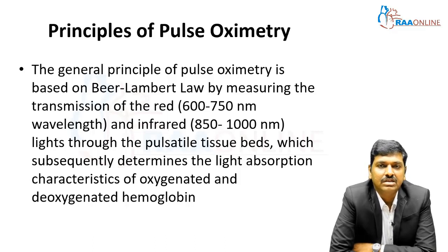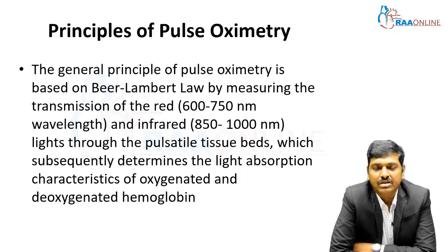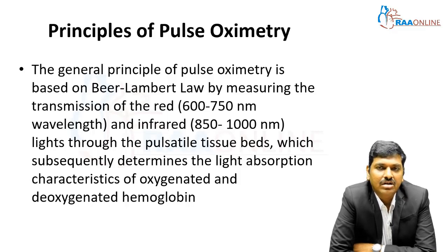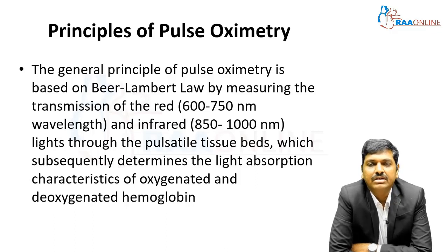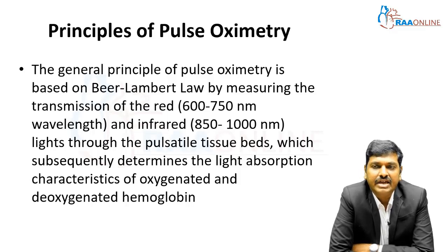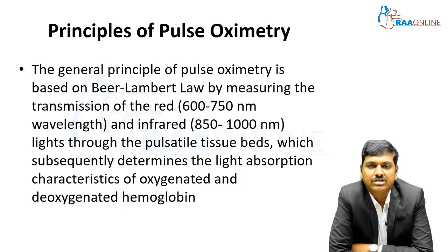The general principle of pulse oximetry is based on the Beer-Lambert law. The device measures the transmission of red light — 600 to 750 nanometer wavelength, in the visible spectrum — and for pulse oximetry, 660 nanometers is usually used. The infrared wavelength used is between 850 to 1000 nanometers, with the precise wavelength being 940 nanometers. This light passes through pulsatile tissue, which determines the light absorption characteristics of oxygenated and deoxygenated blood.